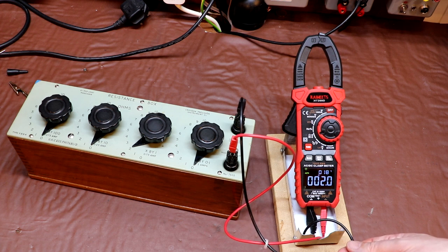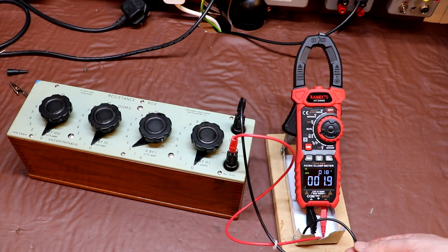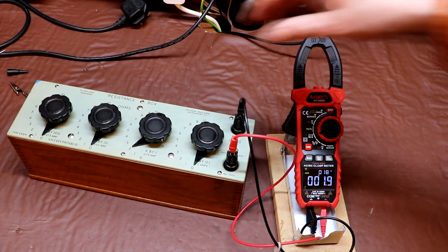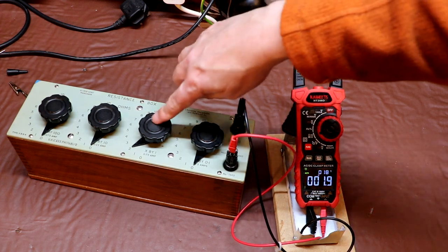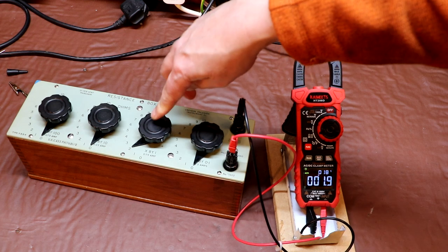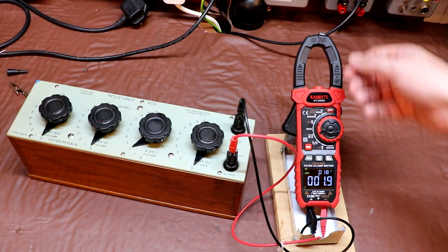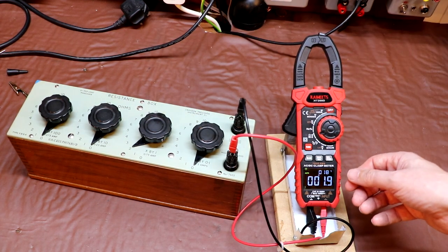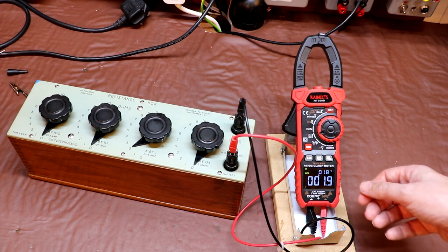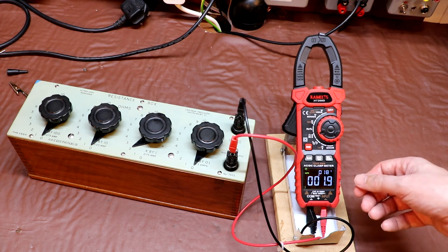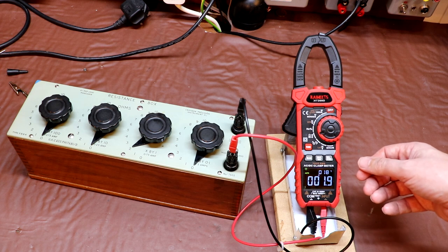Now from time to time it's not unusual to have to extend the length of your test leads, and of course that increases the resistance, so I'm just going to simulate that effect of having long test leads by setting up 2 ohms here on my resistance decade box. But it is really useful to be able to remove this 2 ohm offset from our meter reading, and the way we do that is to use a 0 or a null control.